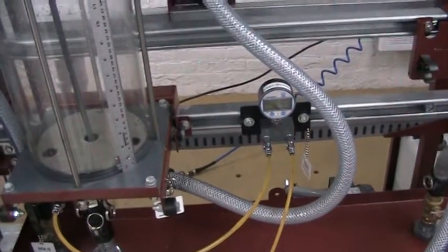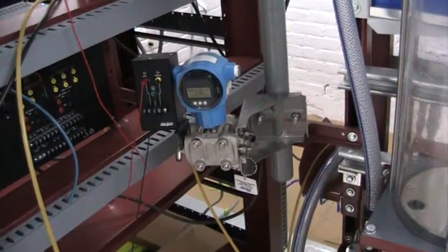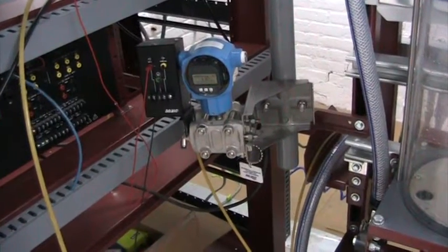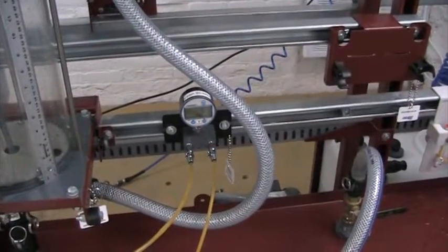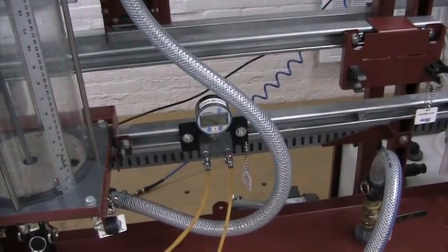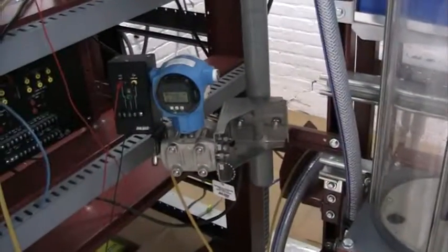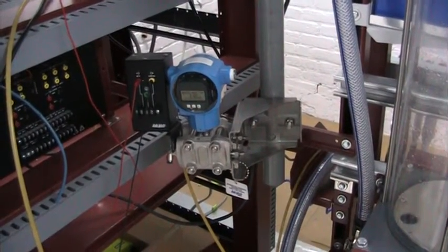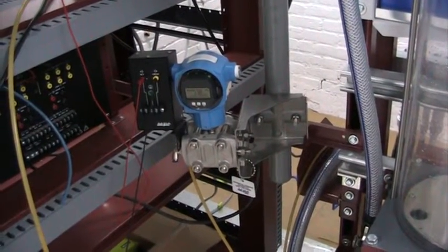First, of course, it's unnecessary to connect the pressure indicator to my differential pressure transmitter, because my differential pressure transmitter can do more than what my pressure indicator can do. My pressure indicator can indicate pressure, gauge pressure, and that's about it. It can't transmit any information to a PLC, for example. Whereas my differential pressure transmitter can do both. It can measure gauge pressure. It can also transmit information. It can do much more than that, actually.